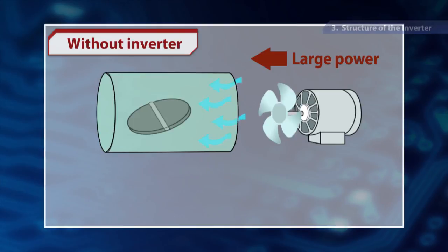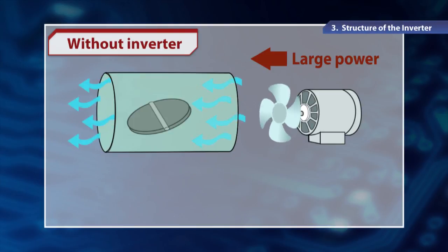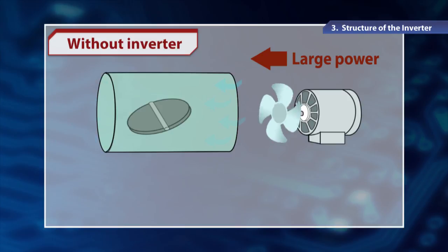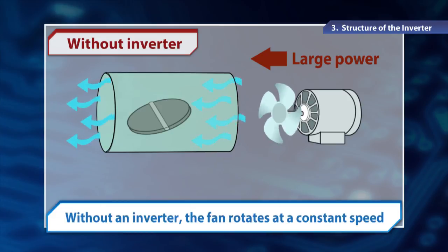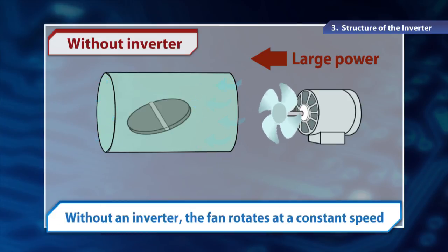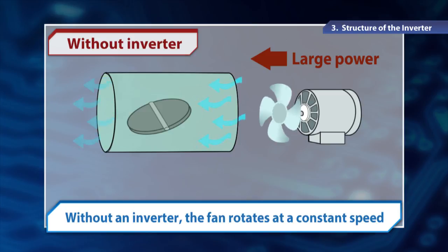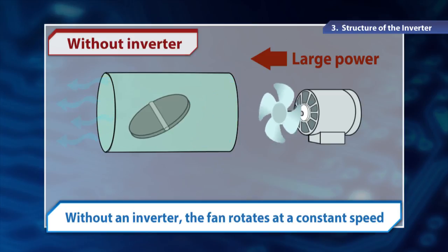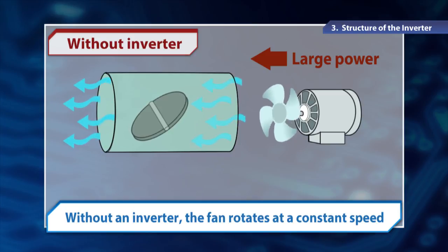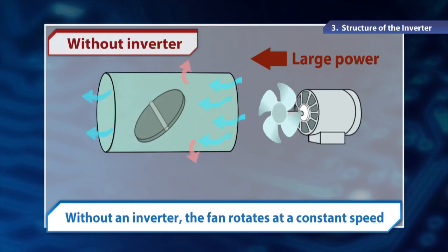When a fan runs without an inverter, but by a commercial power supply at a constant voltage and frequency, the fan rotates at a constant speed. To reduce the airflow, dampers are used, but since the motor continues to use power, it is wasted.